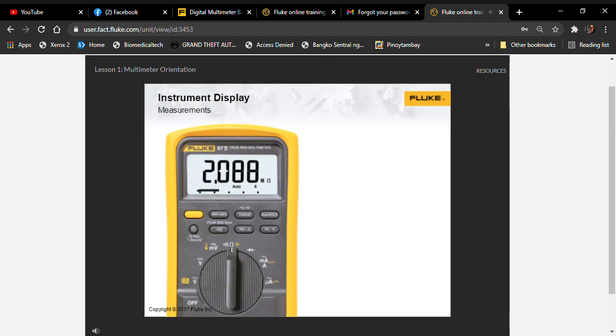Pay careful attention to the units displayed and any added prefix, which is a letter before the unit. The multimeter may add prefixes as needed in order to display the measurement within the number of digits available. For example, when checking an insulator, it's common to measure high resistance in millions of ohms, which are displayed as a capital M with the Greek ohm symbol omega for megohms. A measurement of 2.08 megohms is the same as 2.08 million ohms.